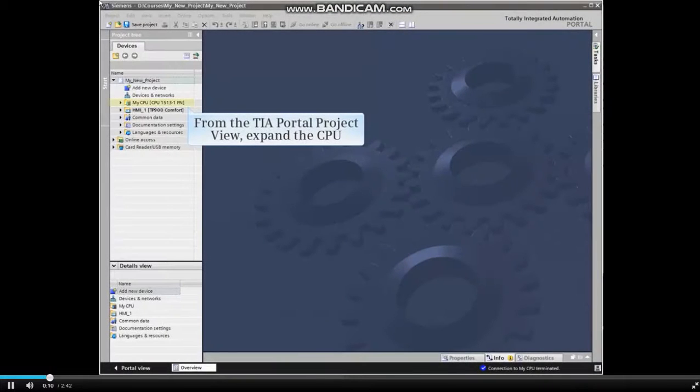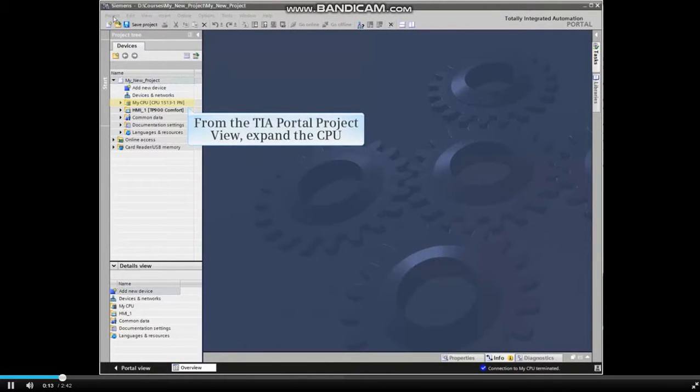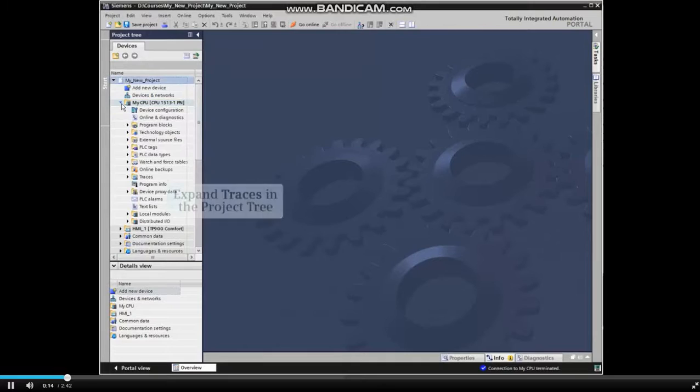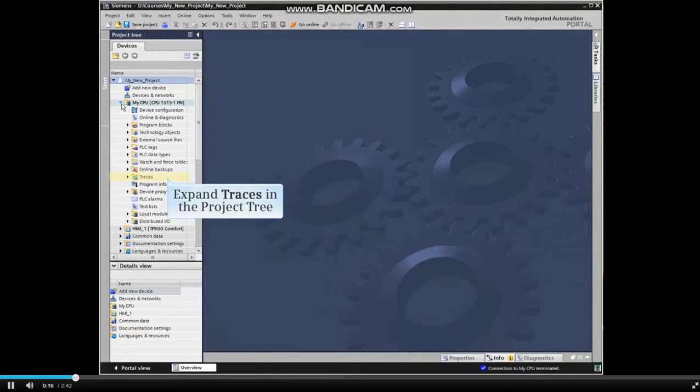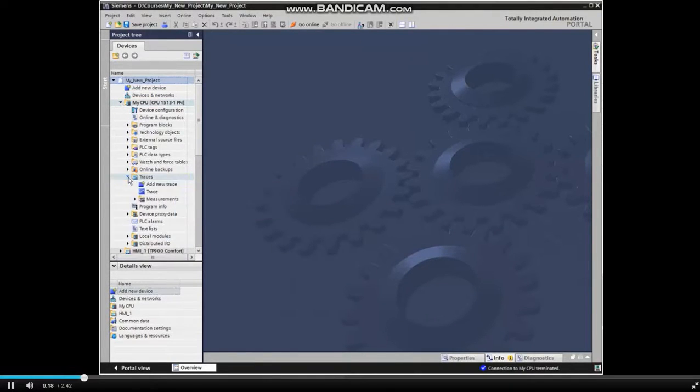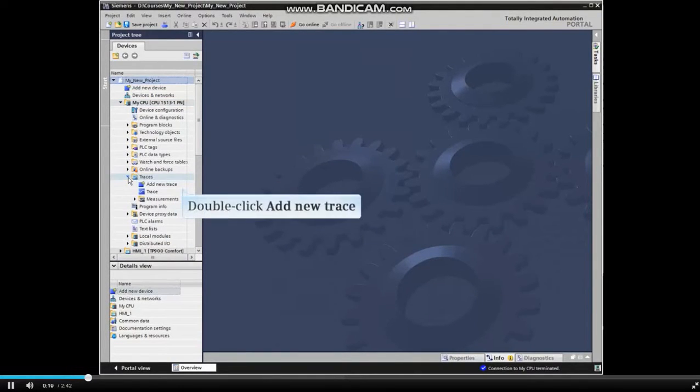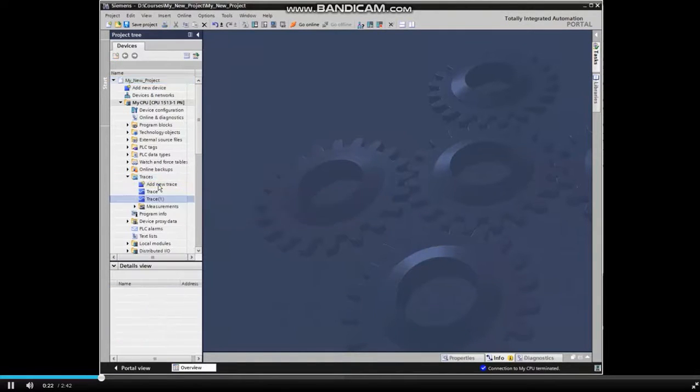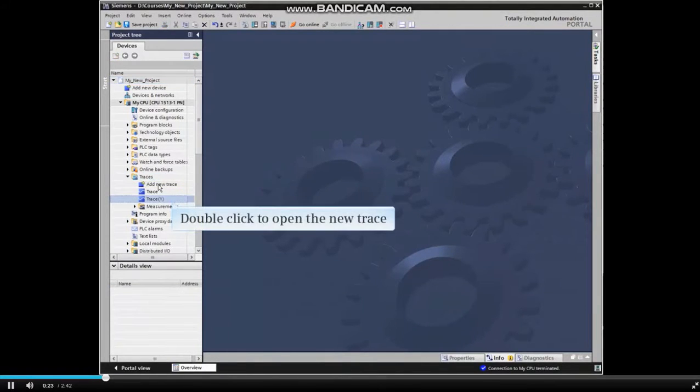From the TIA Portal project view, expand the CPU and traces listings in the project tree. Double-click Add New Trace and double-click the new trace to open it.